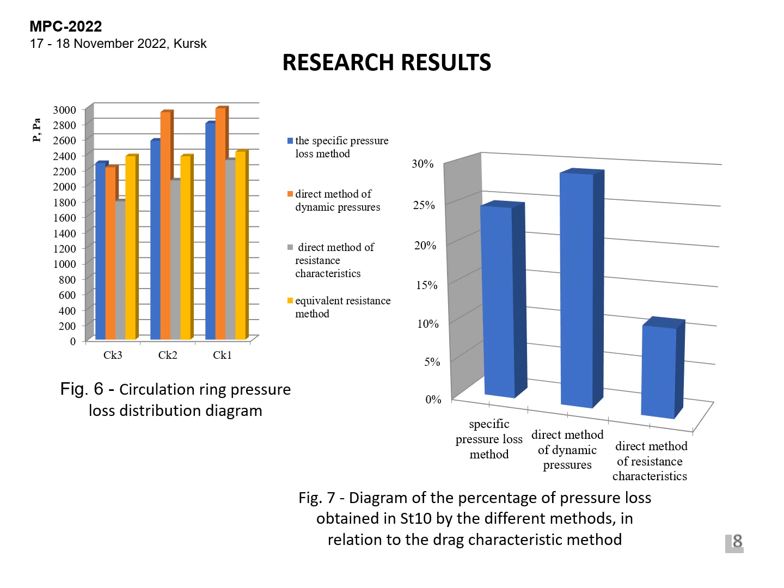According to the results of the forward and reverse hydraulic calculation methods for one of the branches of the heating system, we have obtained the pressure losses of the main and secondary rings, as well as the distribution of flow rates across the risers. Let us present the results of the calculations in the form of diagrams in figures 6, 7, and 8. The main circulation ring CK1 and the two secondary rings CK2 and CK3 pass through riser 10 and riser 8 respectively. Taking the direct method of resistance characteristics as the basic method, we express the deviation of the obtained pressure losses by other methods in riser 10 in percent.